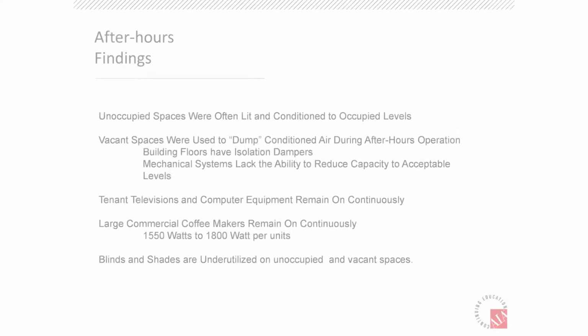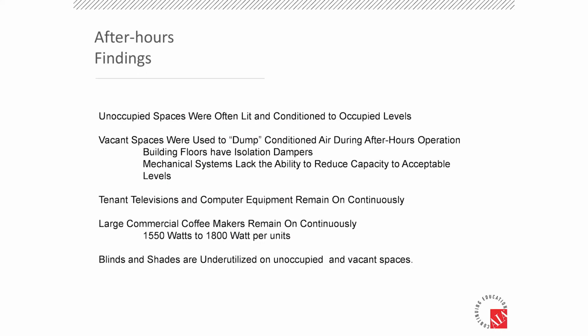So the way the building is divided, you may have one floor that is looking for conditioned air after hours, but the mechanical equipment lacks the ability to reduce capacity for that single floor. So they would just open the dampers and dump air. You'd walk into a vacant space with 68 degrees or 65 degrees space temperature, and the dampers would be wide open on that floor. As we walked around the tenant spaces, the newer spaces did have a lot of items like lighting control, newer controls.